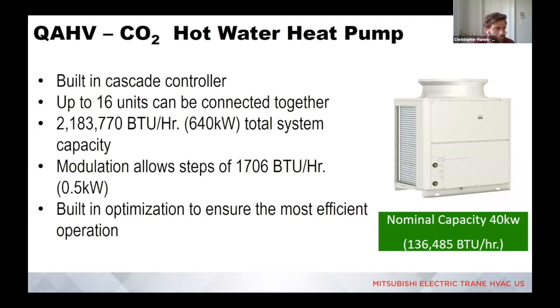Yeah. Sorry, keep going. And then the question was, does that vary? Is there a typical leaving water temperature that you would set during cooling mode, or during the summer, and then a different one during the winter, or does it vary constantly? So just like typical VRF systems, the unit is not designed to target a specific leaving water temperature or even a specific discharge air temperature at the fan coil.